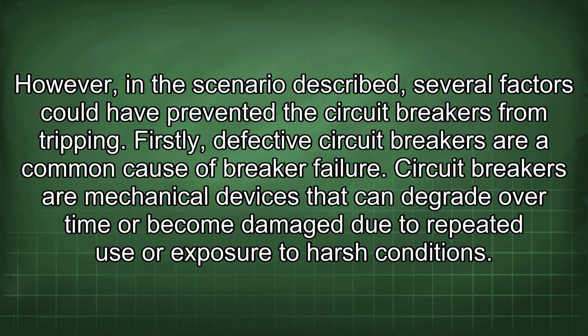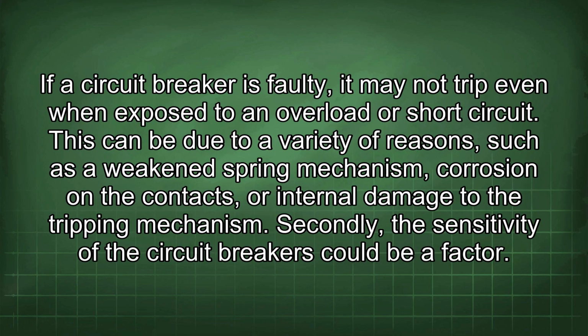Firstly, defective circuit breakers are a common cause of breaker failure. Circuit breakers are mechanical devices that can degrade over time or become damaged due to repeated use or exposure to harsh conditions. If a circuit breaker is faulty, it may not trip even when exposed to an overload or short circuit. This can be due to a variety of reasons, such as a weakened spring mechanism, corrosion on the contacts, or internal damage to the tripping mechanism.